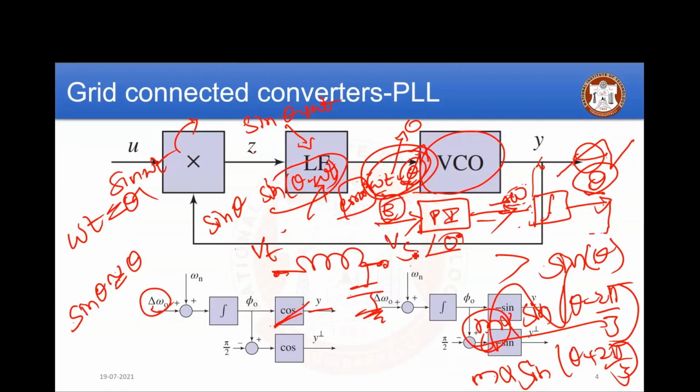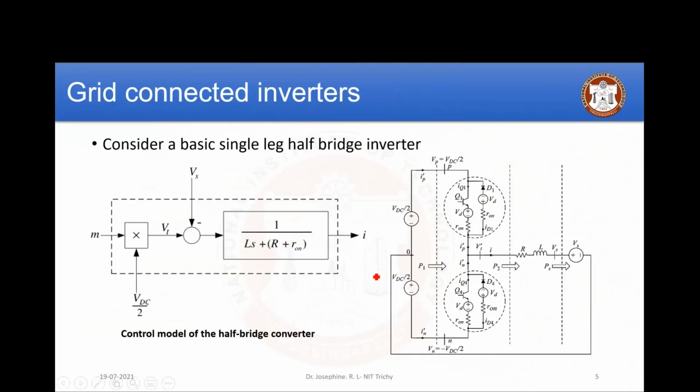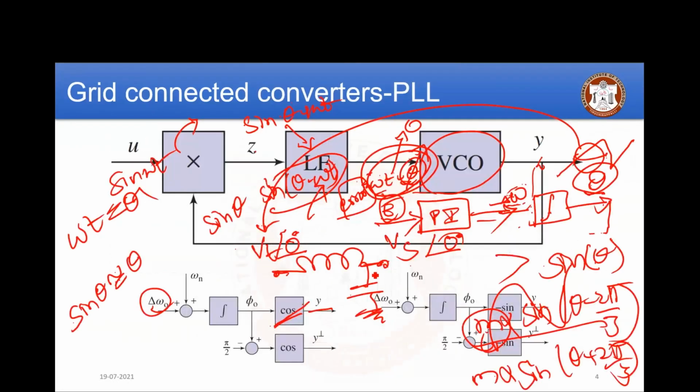Here it is some 0. So if I directly give this P theta here, then I'll get 0. But if I add manually to this theta some value, some theta dash, then because of this phase difference, it is going to inject real power. So this extra theta you will get from some power reference.